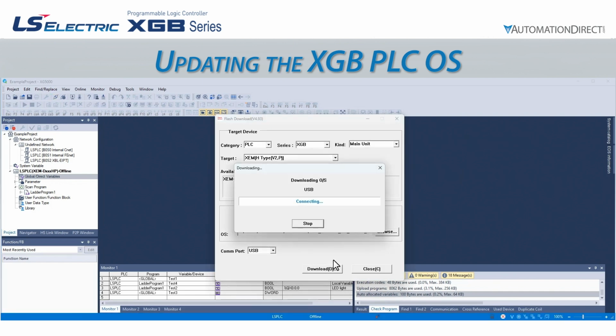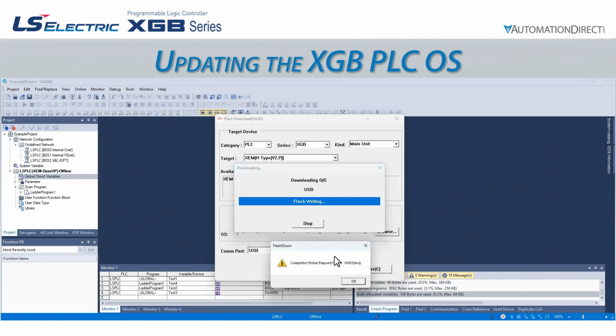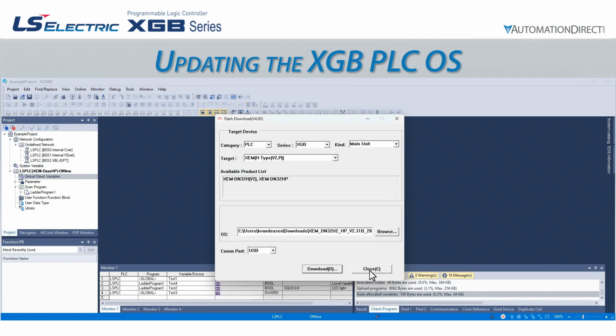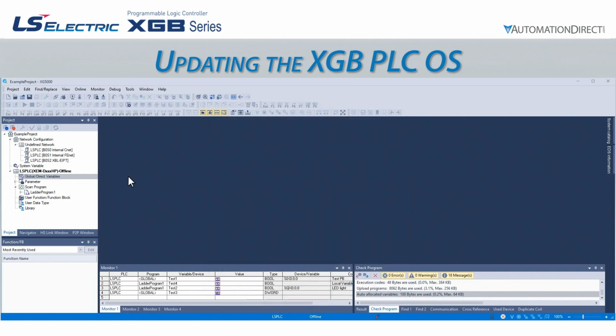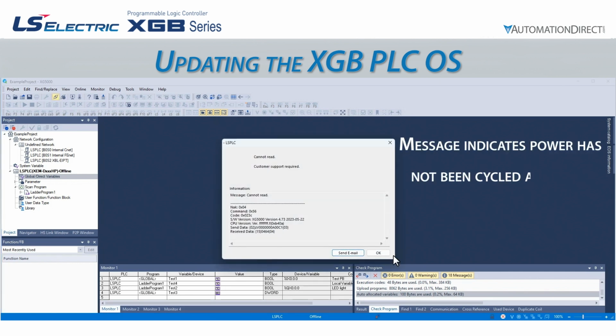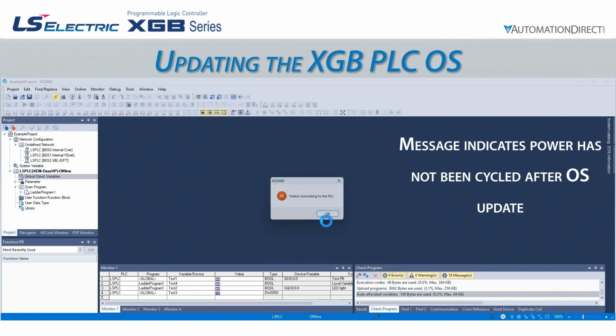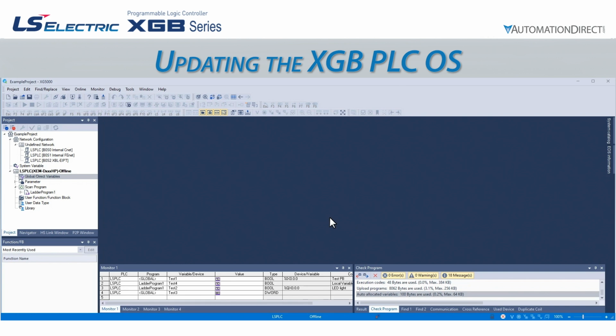If we click Download, we see a progress bar pop up, and when the download is complete, we get a positive confirmation that it downloaded successfully. If there was an issue preventing the download, such as the PLC being in run mode, we would get a different message indicating what the issue was. Now that we have updated the OS, we will need to cycle power to get back online with the CPU. This same process can be used to flash an older OS version to the CPU.